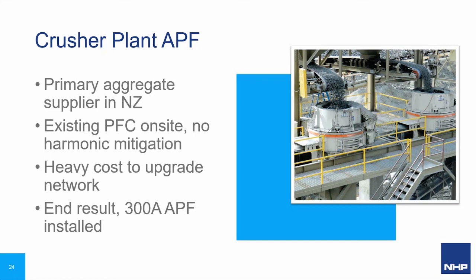Excellent. So what prompted them, though, to look at using an APF? Well, more recently, the quarry management decided to enhance their product quality by changing the main rock crusher from fixed speed to variable speed control. The main shaft of the crusher was originally driven by a pair of 355 kilowatt induction motors, one being started on an NHP supplied soft starter, and the second motor being brought on direct online once the rotor was up to speed. And this was all fine because it was relatively low harmonics.